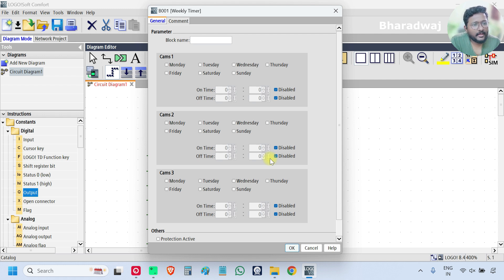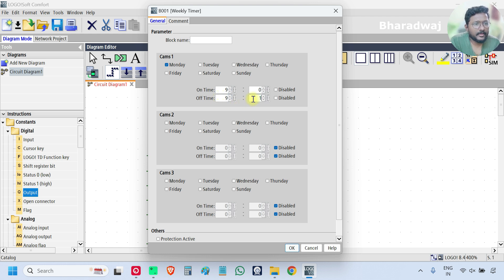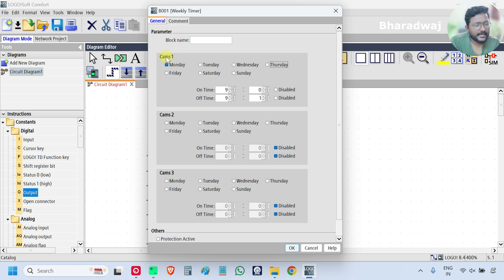Let's suppose every Monday at 9 o'clock. So remove these ticks. At 9 o'clock I want to turn on an output, and after one minute I want to turn off the output — for simulation purpose I am just reducing the time. We can select different days, no issue — multiple days. I am just using Monday. On every Monday, irrespective of the year or month, every Monday at 9 o'clock output will be on, and after one minute output will be off. So we will test this.